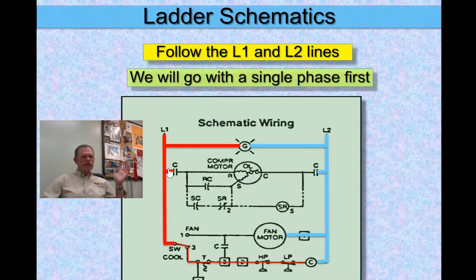All right, here I don't have a circuit, but I've got potential. I've got L1 to one side of the contactor, L2 to one side of the contactor. The contactor switches are open, so I've got no circuit. Down here in the fan motor circuit, I've got L2 to the fan motor, but that's it. I don't have anything else happening.